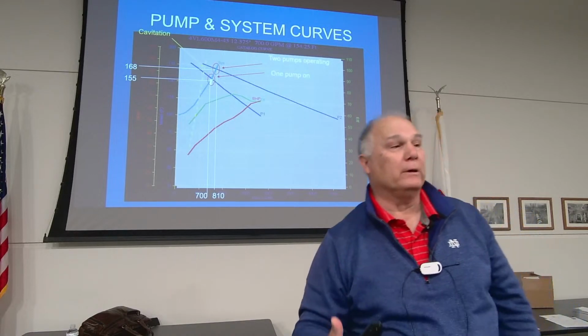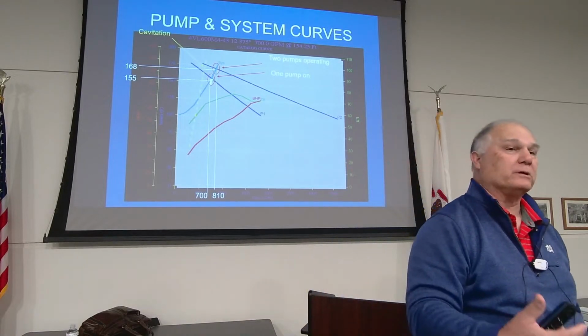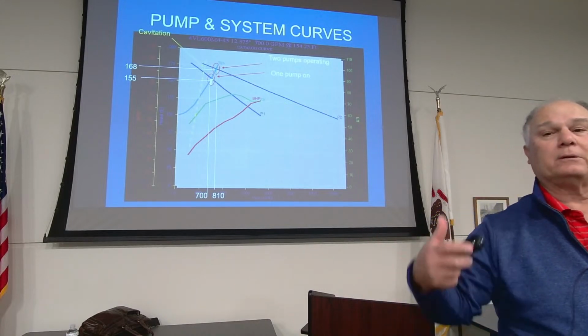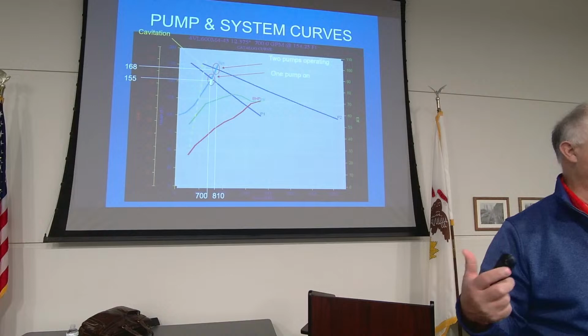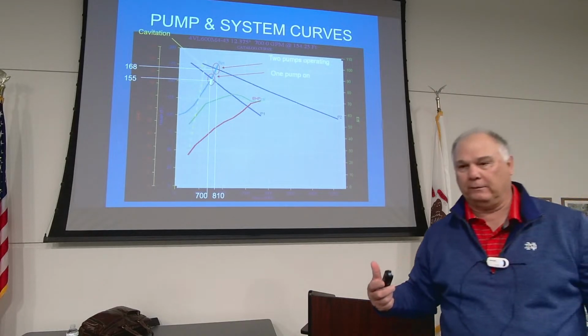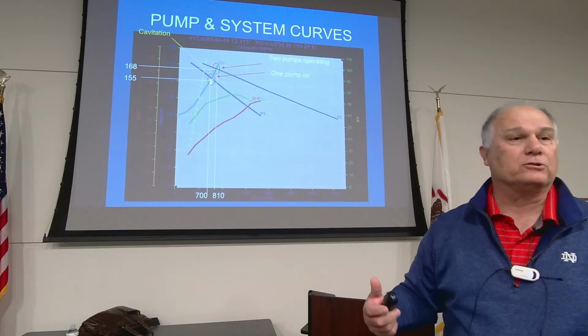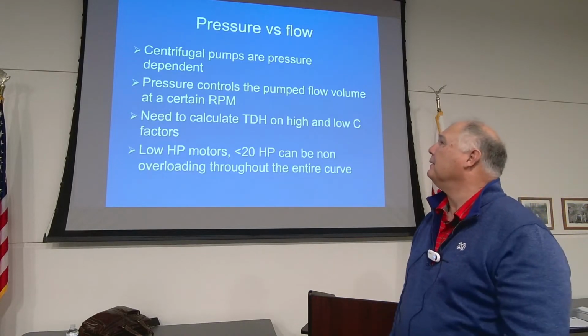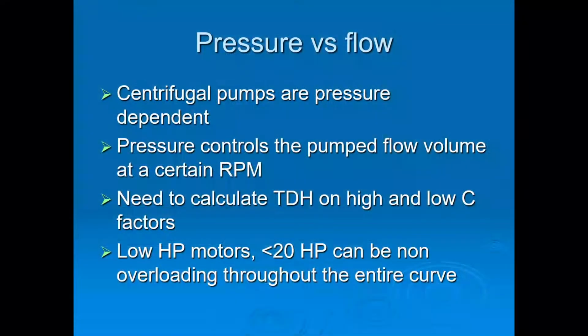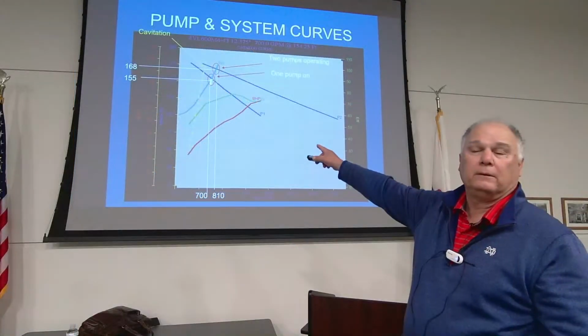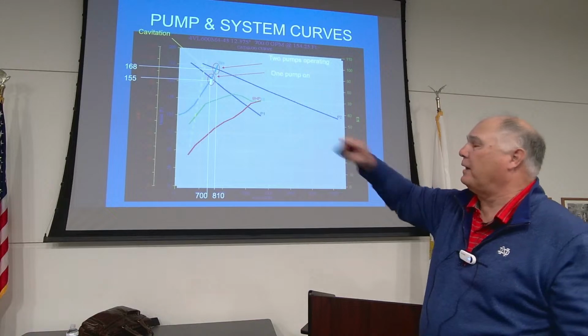So impeller selection and understanding what's going to happen is important. In that station, doing an extra 110 gallons a minute has no benefit to anybody, virtually. It's actually going to give you more limitations. But pumps are not based on volume alone; you get the volume based on the head they produce against. If you go back to this curve, that one pump can do all the way out to 1,500 gallons a minute if it only had 60 foot of head on it.